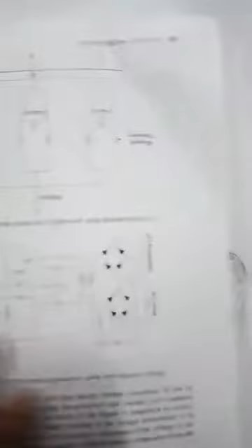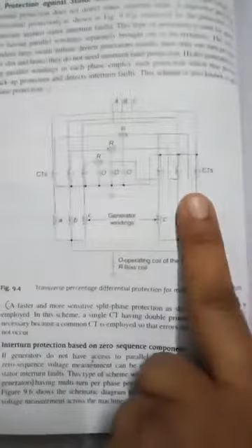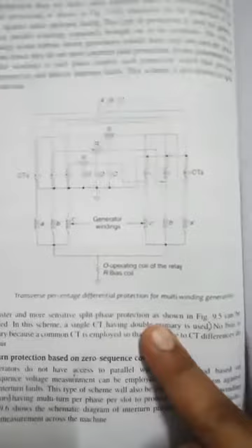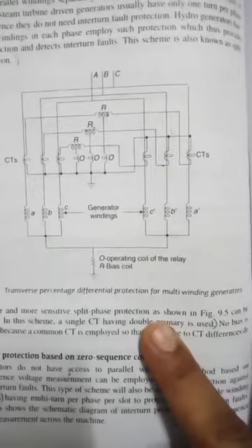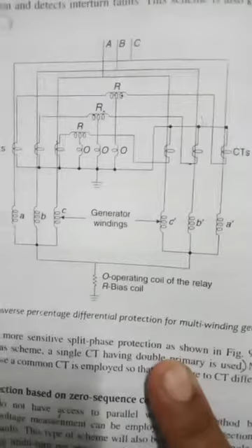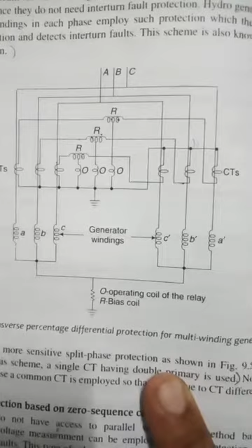Next is, with a neat diagram, explain the construction and working of the stator interturn protection scheme. So this is a very repeated question. Stator interturn protection scheme: longitudinal percentage differential protection does not detect stator interturn faults. A transverse percentage differential protection, as shown in the figure, is employed for the protection of a generator against stator interturn faults. So this type of protection is used for generators having parallel windings separately brought out to the terminals.